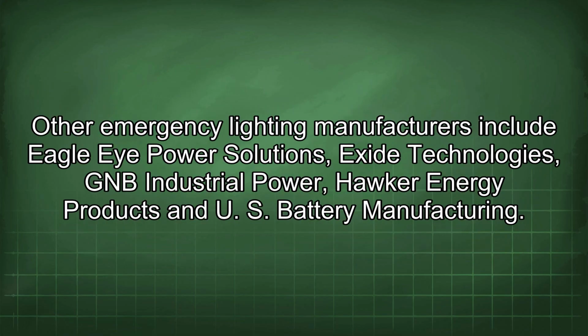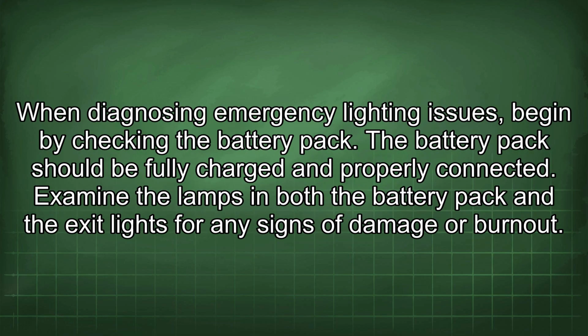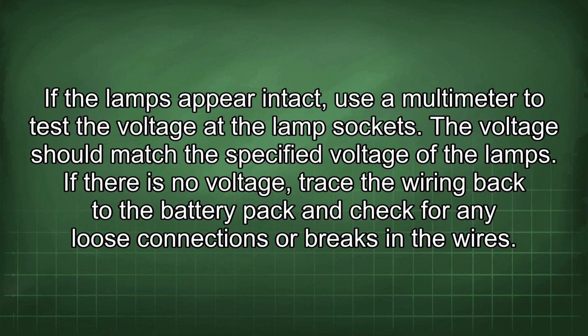Other emergency lighting manufacturers include Eagle Eye Power Solutions, Exide Technologies, GNB Industrial Power, Hawker Energy Products, and U.S. Battery Manufacturing. When diagnosing emergency lighting issues, begin by checking the battery pack. The battery pack should be fully charged and properly connected. Examine the lamps in both the battery pack and the exit lights for any signs of damage or burnout. If the lamps appear intact, use a multimeter to test the voltage at the lamp sockets. The voltage should match the specified voltage of the lamps.